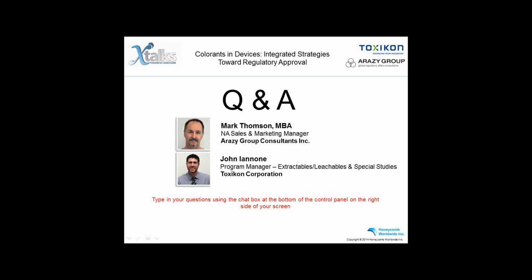Also a good question. When we're talking about colorants and better characterizing and evaluating the impact of a colorant from a device, certainly the longer the contact the device has with the patient, the more of an impact it will have in terms of leachability and therefore bioavailability, going back to the previous question. Now, we have seen, even with limited exposure devices, that sometimes be a concern. It's usually more attributed to if there's some type of delivery of a drug product or a solution for limited exposure.